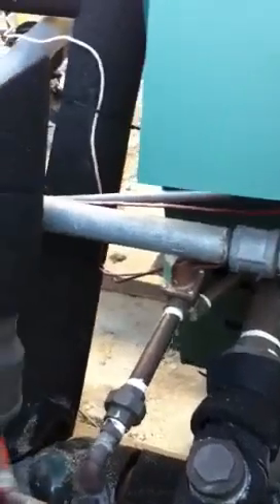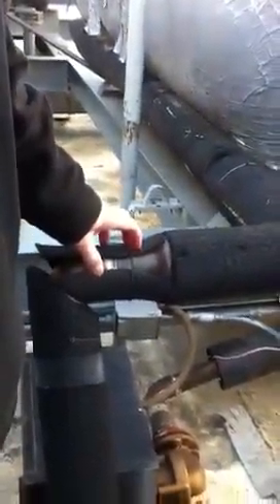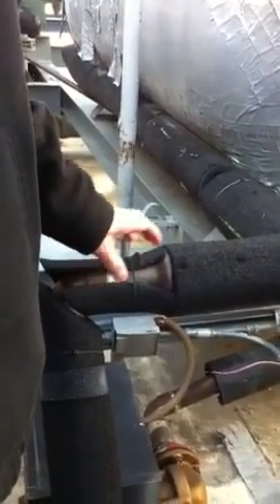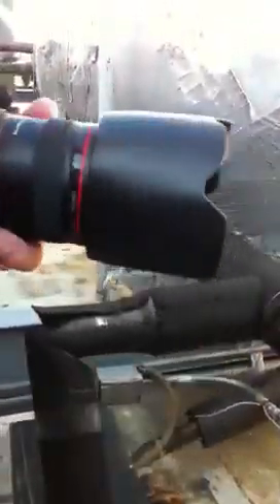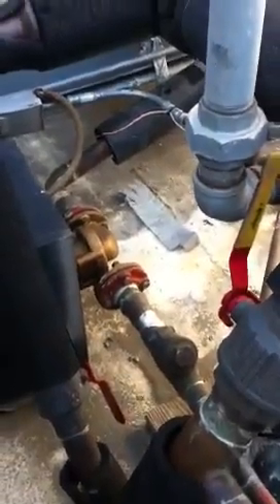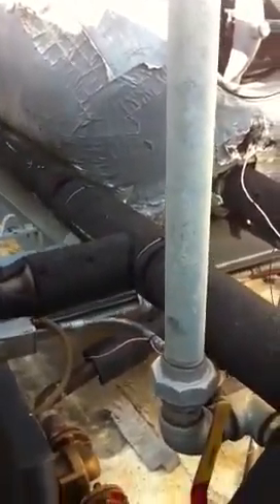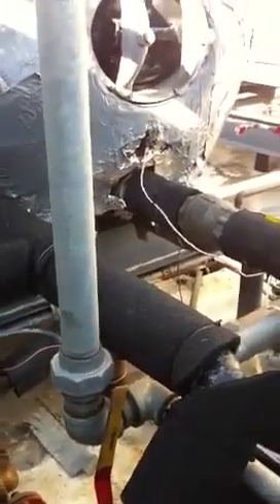In other words, the flow of water is going this way, down and into the boiler. And this really needs to be on the outlet pipes of the boiler, so it circulates into the tank and not through the boilers first. So this is incorrectly done? Yeah, this is wrong. This will be switched to the outlet pipe of the boiler. Okay. Yeah. That's a pretty bad mistake from the prior. Yeah, it's not bad, it's just inefficient. Okay, got it.